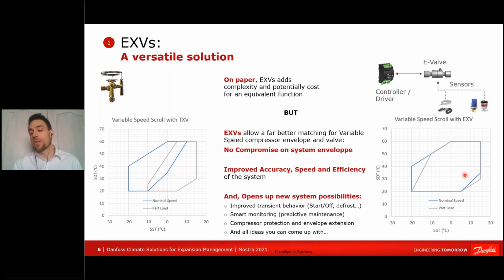right here, because you see that with an EXV, the very same compressor, which is a variable speed VZH we have at Danfoss, you plug in with an E-valve, which is in that case a Colibri valve, and you see that the part load and the full load envelope are matching quite a bit better than what you had with a TXV, meaning that with the electrical valve, you're able to match much more of the envelope of the compressor, and this is what you want. You don't want the valve to limit the capability of your compressor that is maybe 10 times the price of what you pay for the valve.